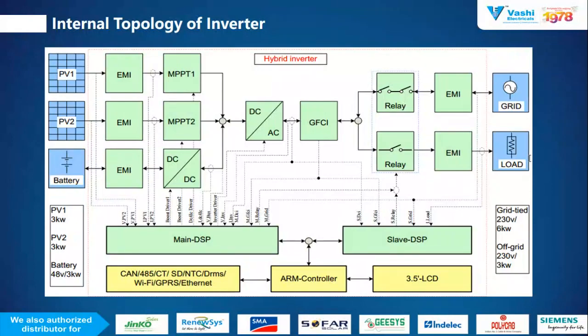So this is the internal topology of the inverter, where you can see MPPT1, MPPT2, and your DC to DC conversion part. On the output side, you can see there is a relay part through which your contact is turned on and off. Whenever any fault occurs, it will open the relay connection, and whenever the fault is solved, it will reconnect the relay. So it will connect with the grid and load whenever you clear the faults. This is the internal topology of the inverter, which gives you a briefing of how it normally works.